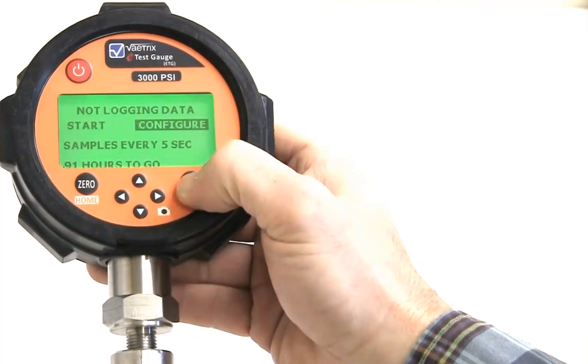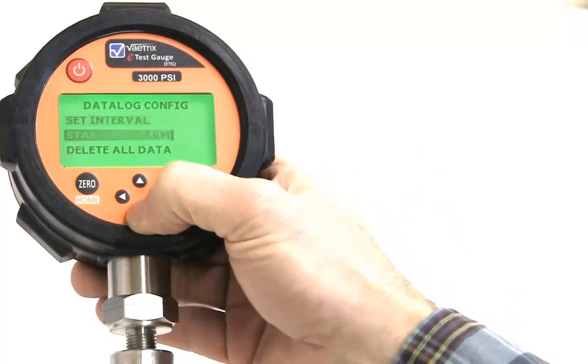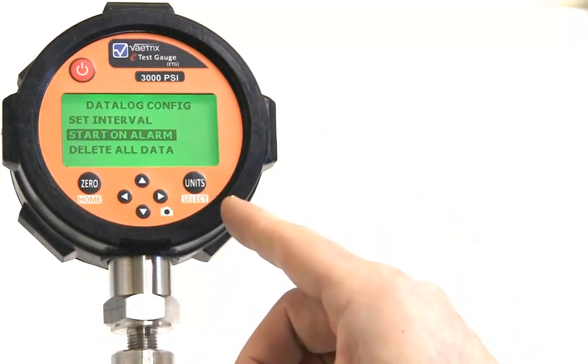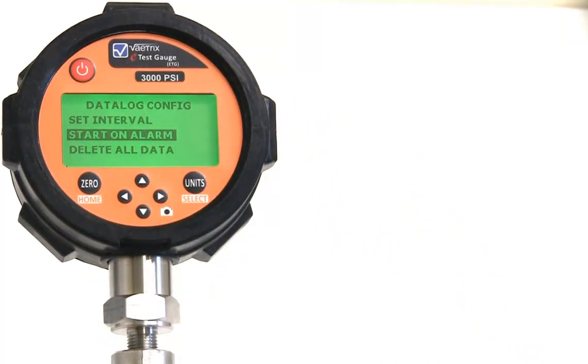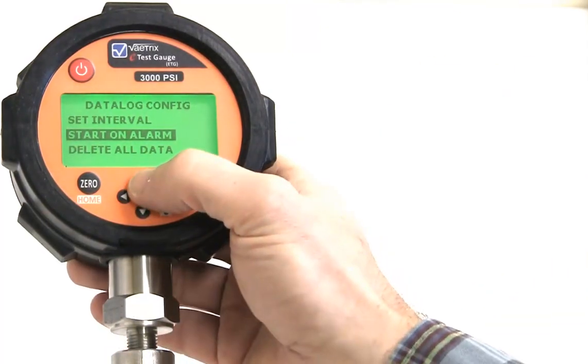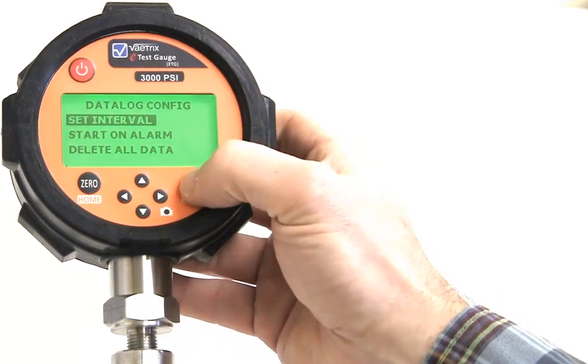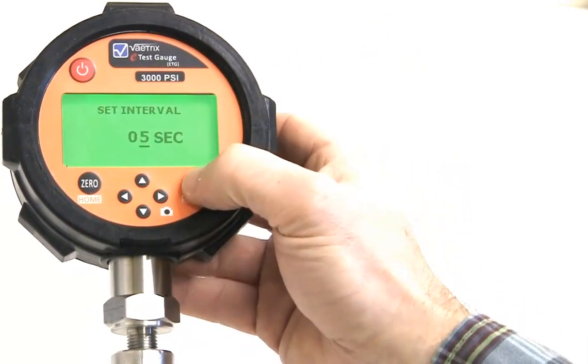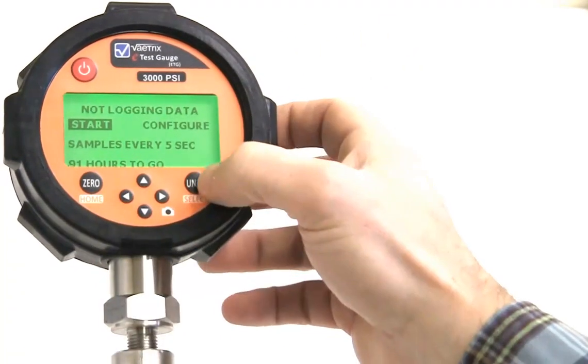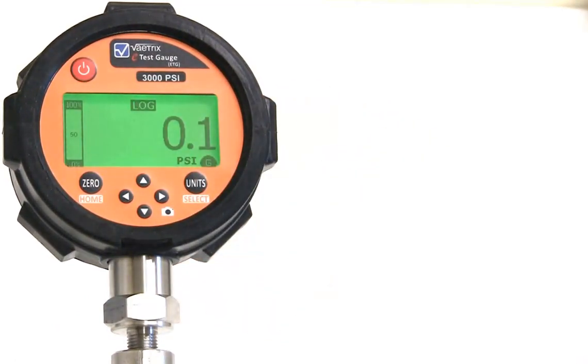Now, one other thing that you saw in the menu was the ability to start on alarm. So if I selected this and had either a high or low alarm set, based on the PSI or whatever engineering unit you were using, it would automatically start the data logging session. So once again, interval 5 seconds, good to go. So I can start. So right now it tells you I'm logging. So it's recording, taking readings every 5 seconds and recording that in the memory in the gauge.